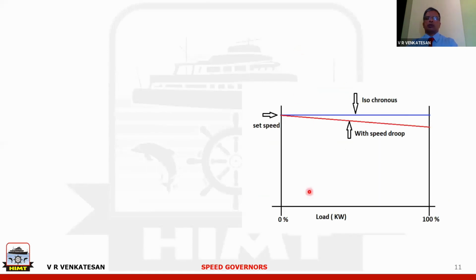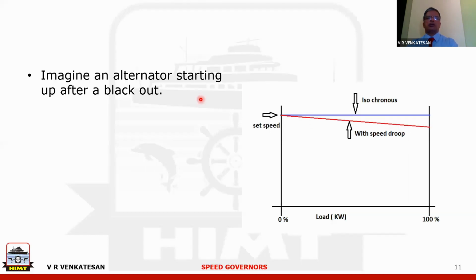So isochronous means, if you see here, or if you take an alternator as an example, the kilowatt of the alternator goes from 0 to 100%, and the RPM will be maintained the same, as you see in blue color. This is called isochronous. If you say there is droop, then as the load increases, the speed will come down. So why the speed is coming down will be seen. But to understand this whole process, start like this.